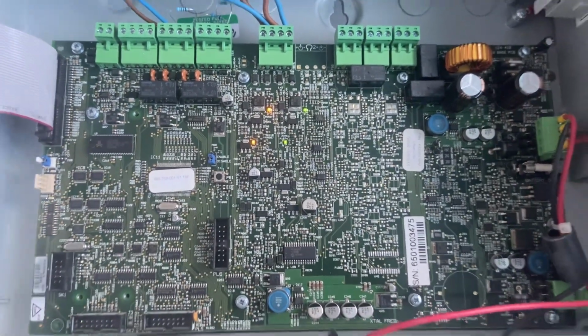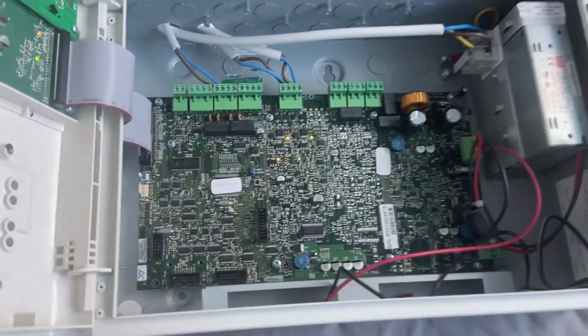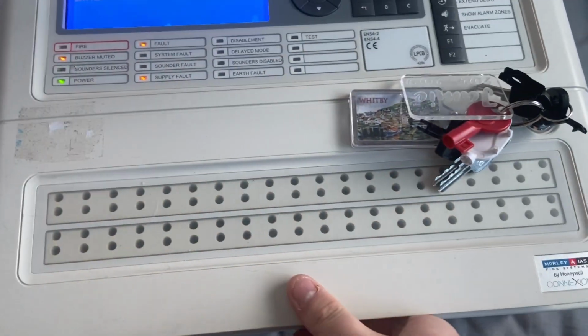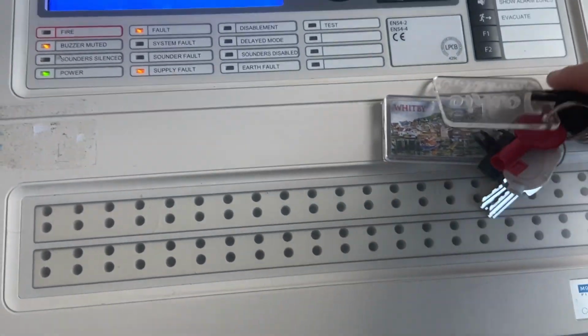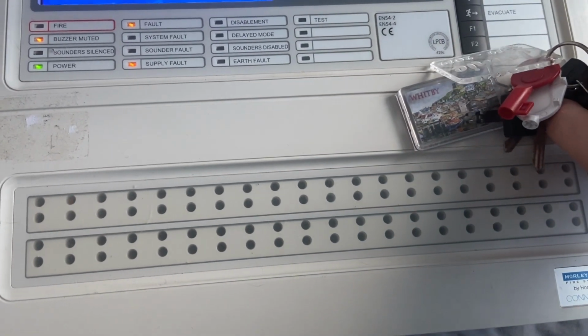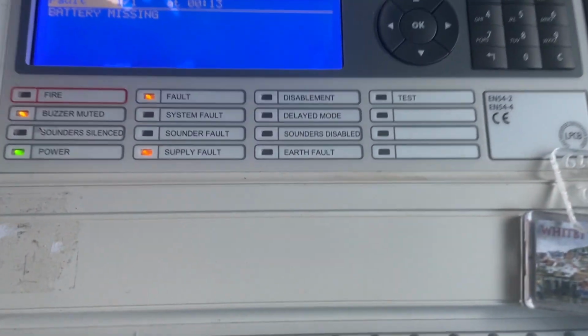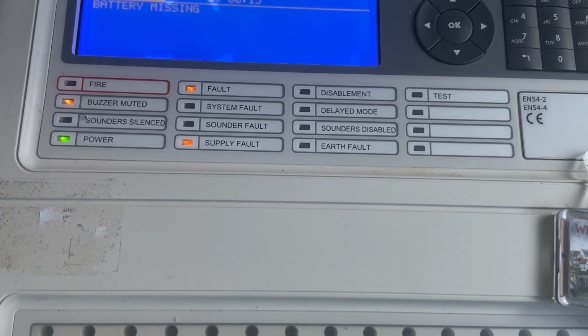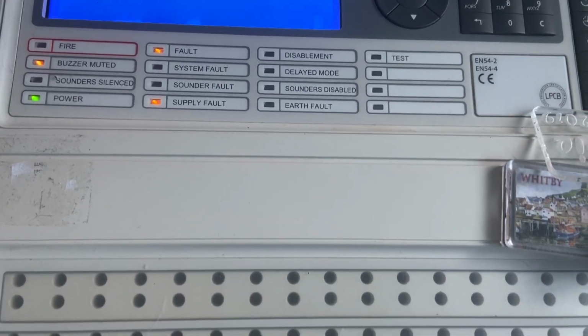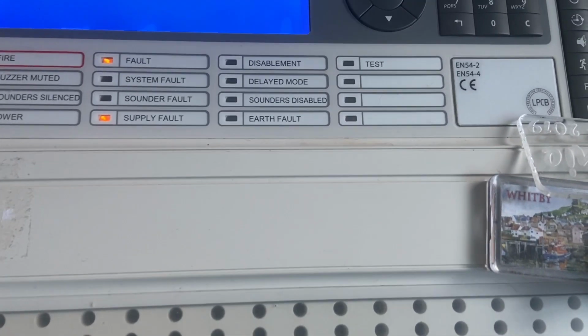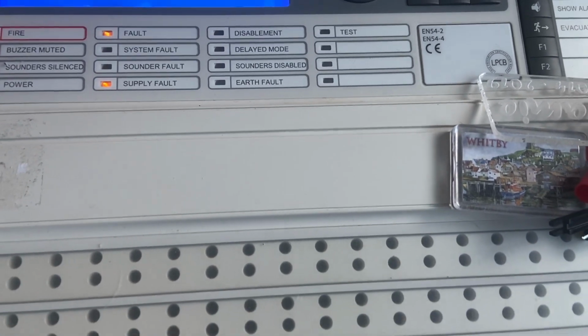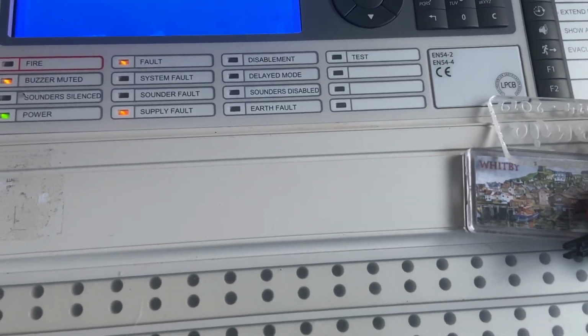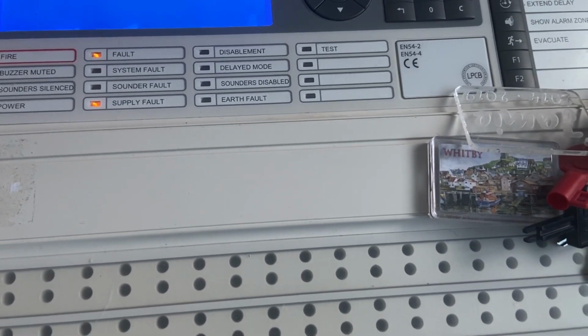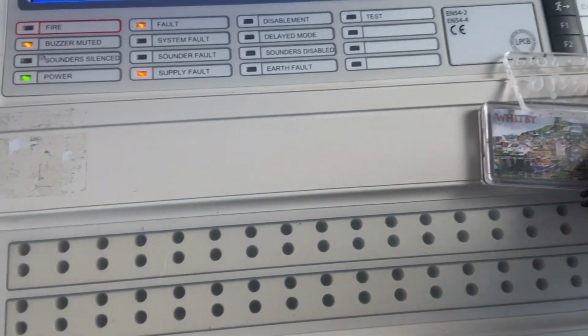So yeah, this panel is basically multi-protocol, which means you can use different protocols on this panel. So this particular panel can accept Apollo, Hochiki or System Sensor. But you can only use one protocol at a time. So I'm currently using Apollo just for this video. So yeah, it's on Apollo at the moment.